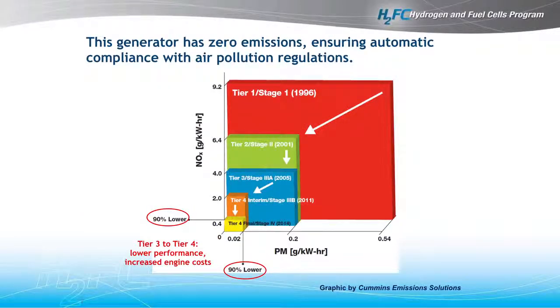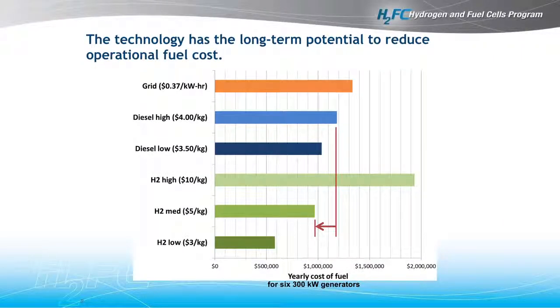In relation to the emissions, this graph is demonstrating since 1996 the changes in emissions requirements for diesel and how that cost increases moving through the stages. So to get down here to this ultimate goal requires about 30% of the total cost of the generator set for diesel. And if you go directly to fuel cells, you get to that zero emission right away without having to make that transition. So that is an advantage. In terms of fuel cost, the potential is there for hydrogen to be on par, if not a little bit better in cost than diesel. Right now, it's not the case, but there's definitely potential. So that's the main drive from this slide.